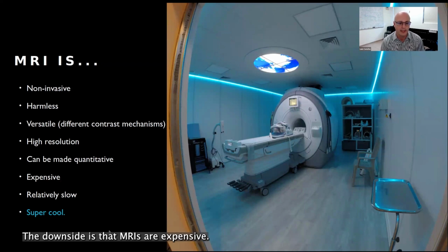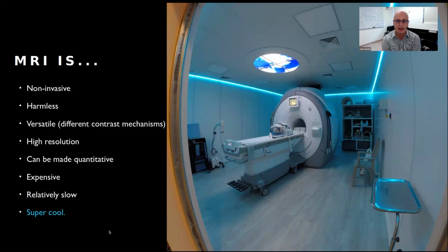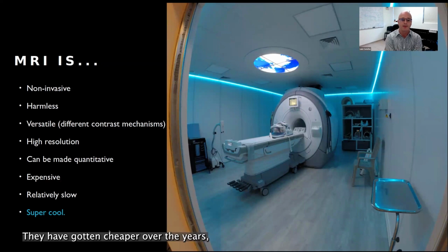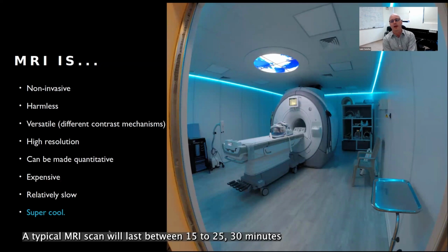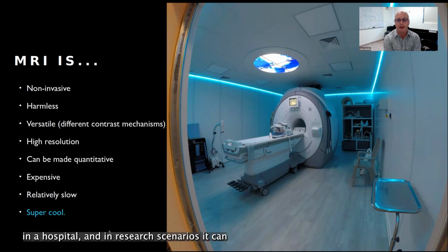The downside is that MRIs are expensive. Not all places can afford an MRI. They have gotten cheaper over the years, but they are still a very heavy investment for any hospital, for any institution. Imaging is relatively slow. A typical MRI scan will last between 15 to 25, 30 minutes in a hospital, and in research scenarios, it can range up to 1 hour maybe.